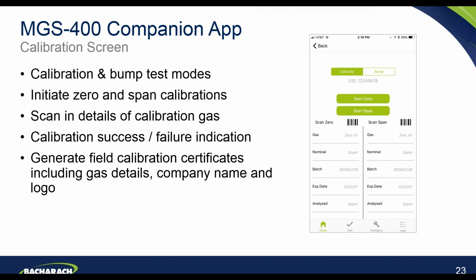Essentially, once you initiate a calibration, you attach your cylinder of calibration gas to the detector, you switch that on and you click start span. It will automatically go through that calibration procedure for you, make any necessary adjustments, and it will tell you if the calibration was a success or a failure. A failure may be if there was some sort of fault with the sensor perhaps.